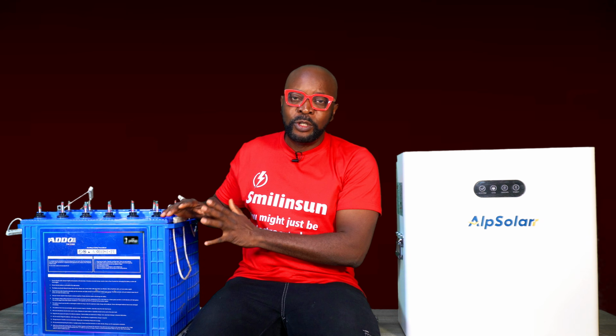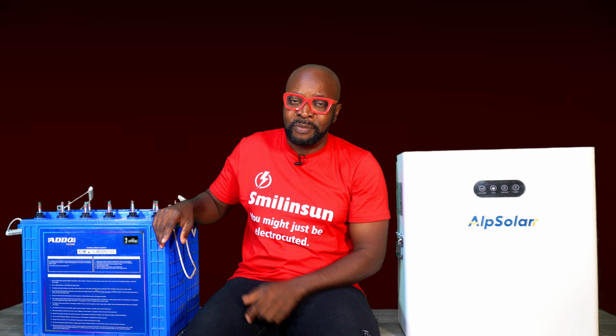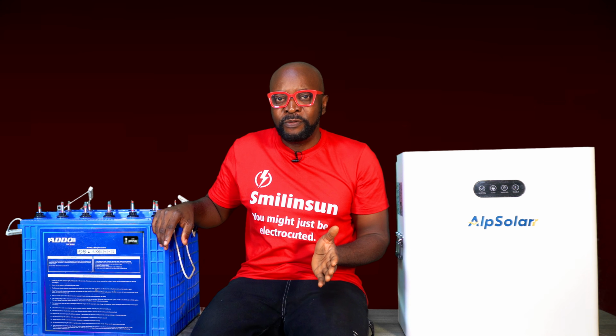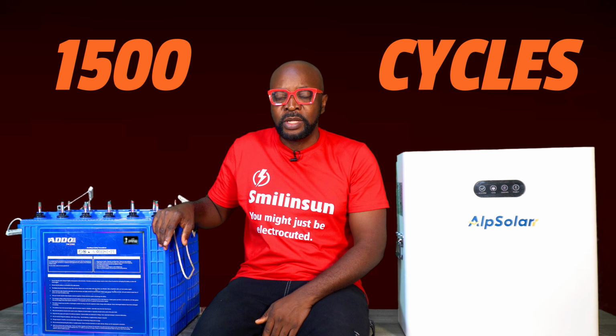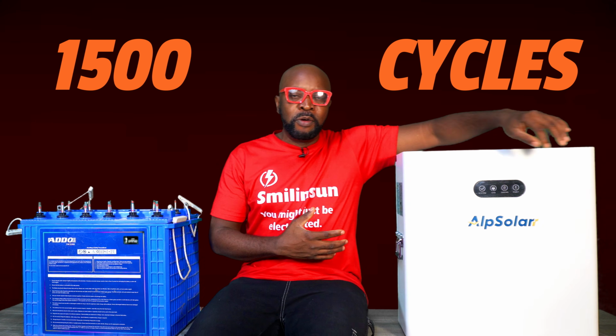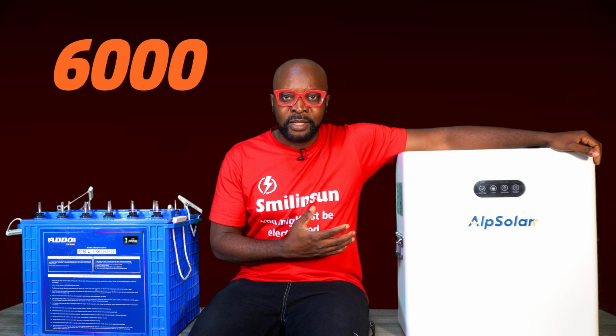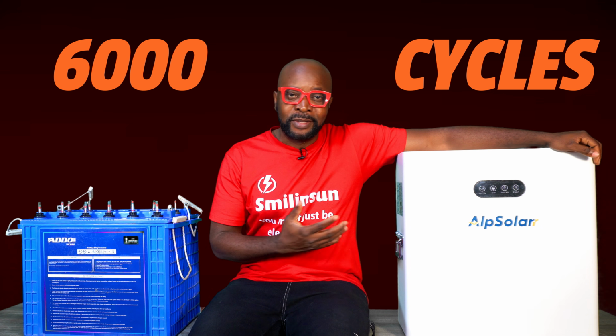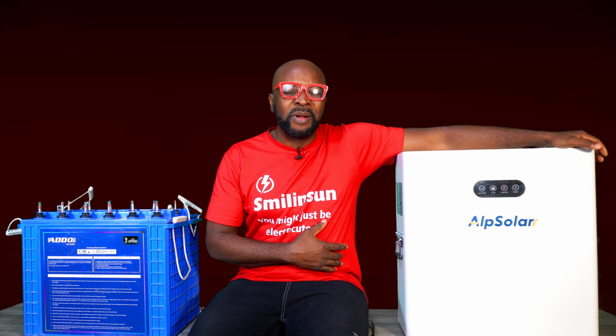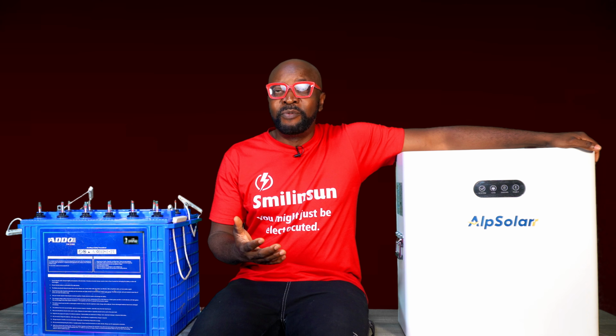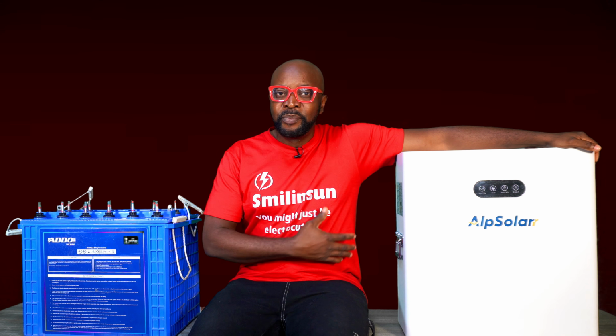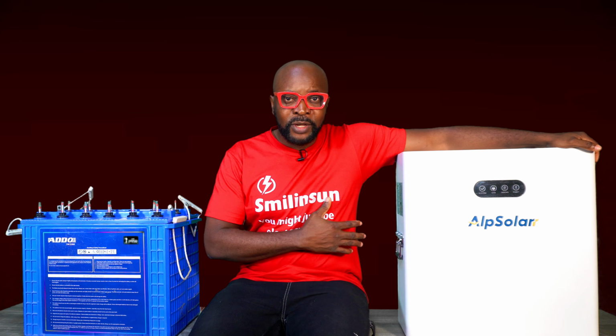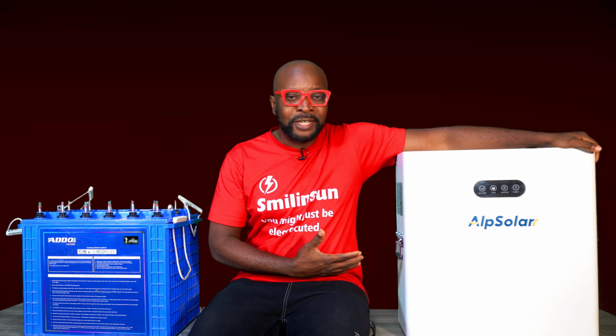So the lifespan of the tubular battery, which is the flooded lead acid battery, is around 1,500 to 2,000 cycles. But the life cycle for the lithium battery is around 6,000 cycles. Okay, so 6,000 cycles is approximately, if you're going at a depth of discharge of like 80% and you're gone completely off grid, there's no support from the grid, this battery is meant to last for 16 years.